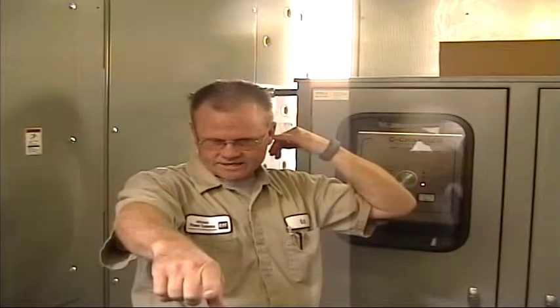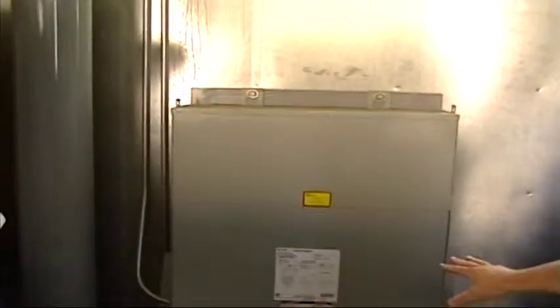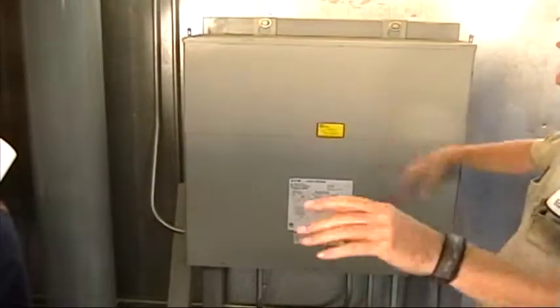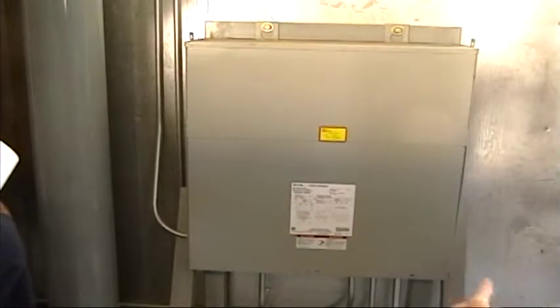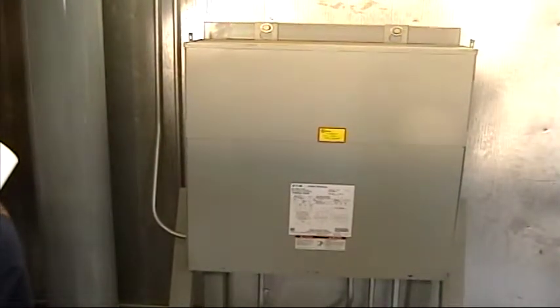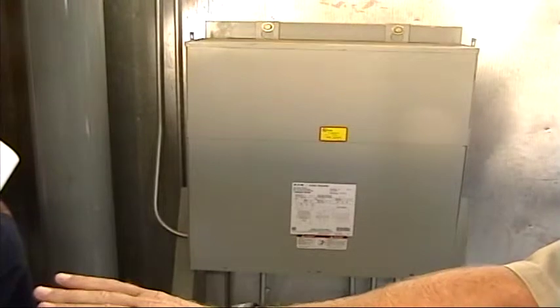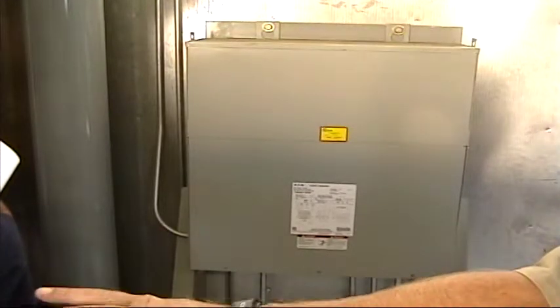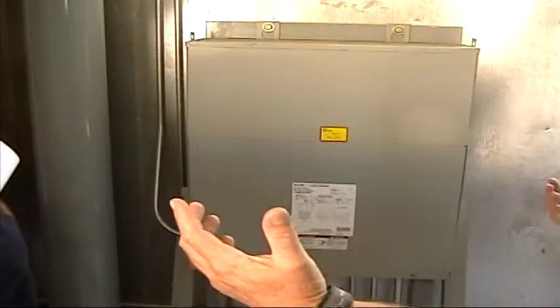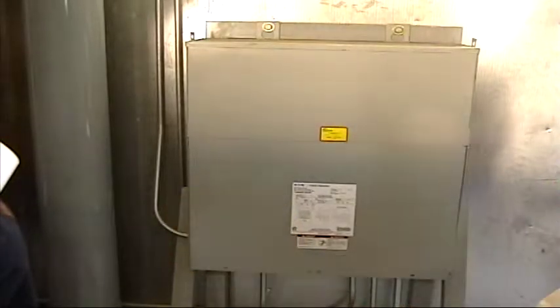One thing to look at, Nathan, swap around to that panel. There's breakers, AC breakers in here that control the lights, the battery charger, the louvers in the back, and the generator space heater. The generator space heater right now is shut off because it's been so warm, you really don't need it.